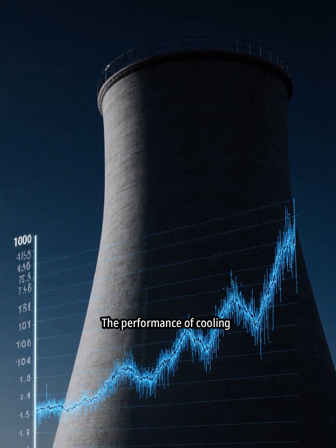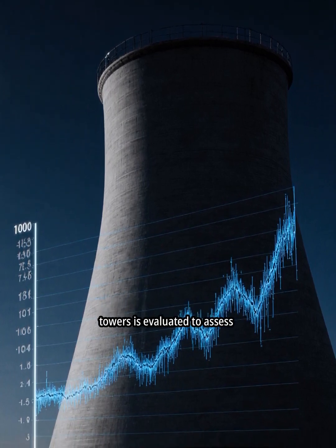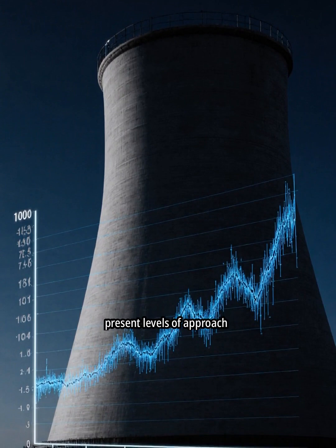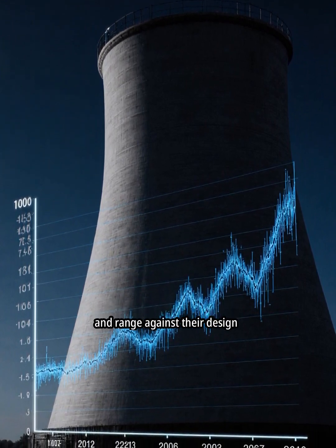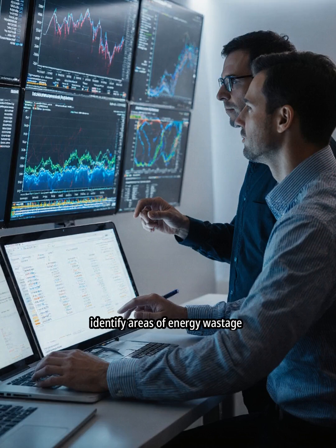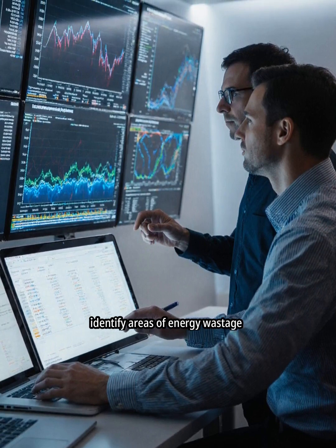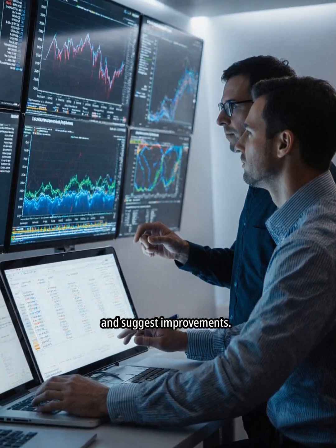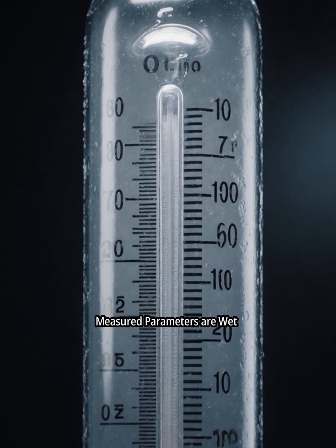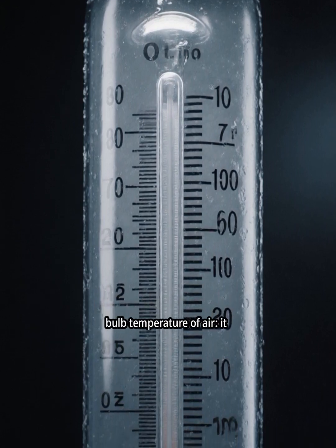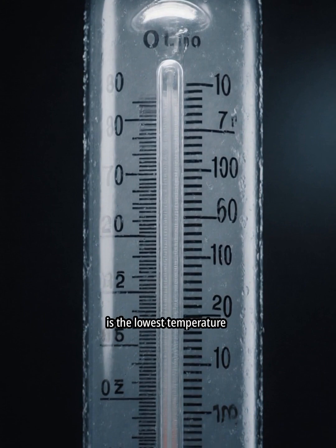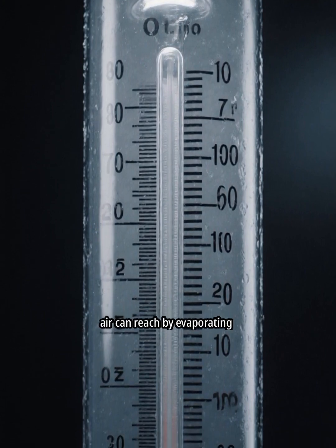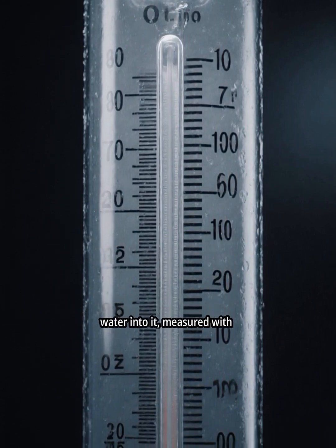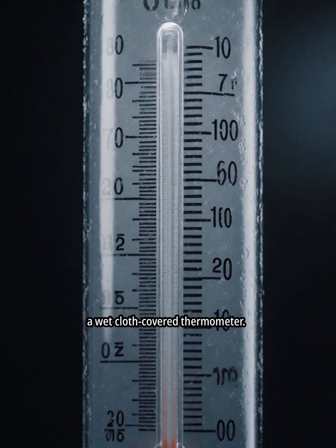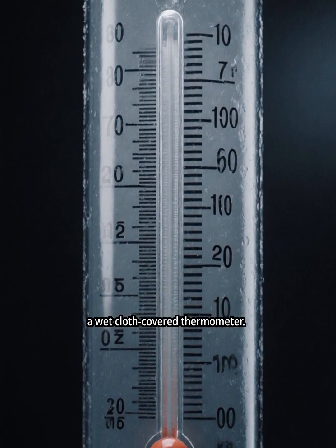The performance of cooling towers is evaluated to assess present levels of approach and range against their design values, identify areas of energy wastage, and suggest improvements. Measured parameters are wet bulb temperature of air. It is the lowest temperature air can reach by evaporating water into it, measured with a wet cloth-covered thermometer.